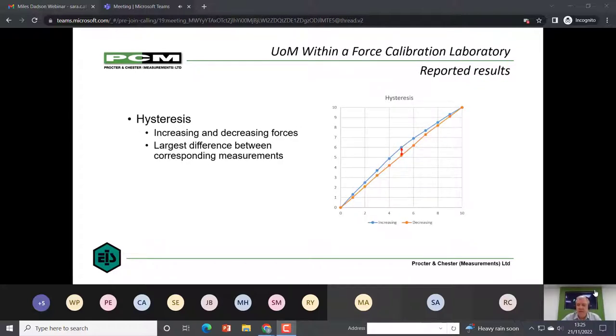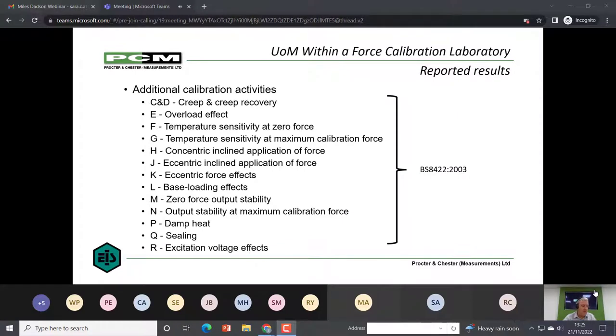Then we come to hysteresis. Hysteresis is the difference between increasing values and decreasing values, and generically you would give the largest deviation between an increasing run and a decreasing run. However, those are just the very simple calibrations, and to be honest, 99% of everything that most calibration labs will produce. However, 8422 and some of the others offer you an awful lot more.